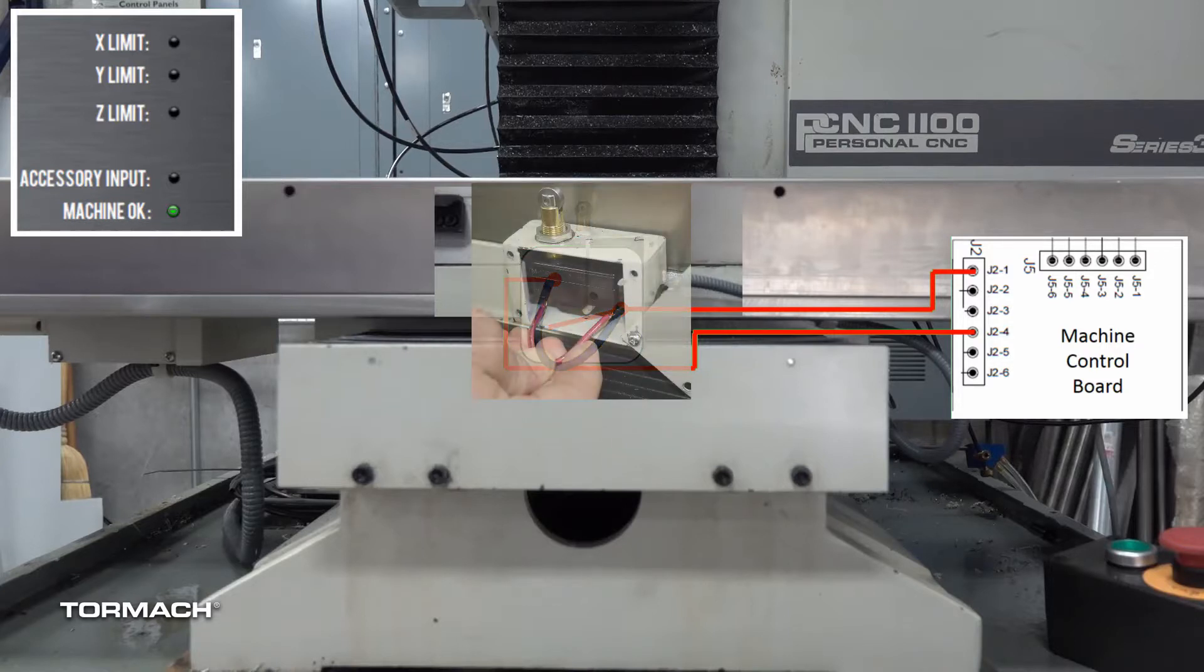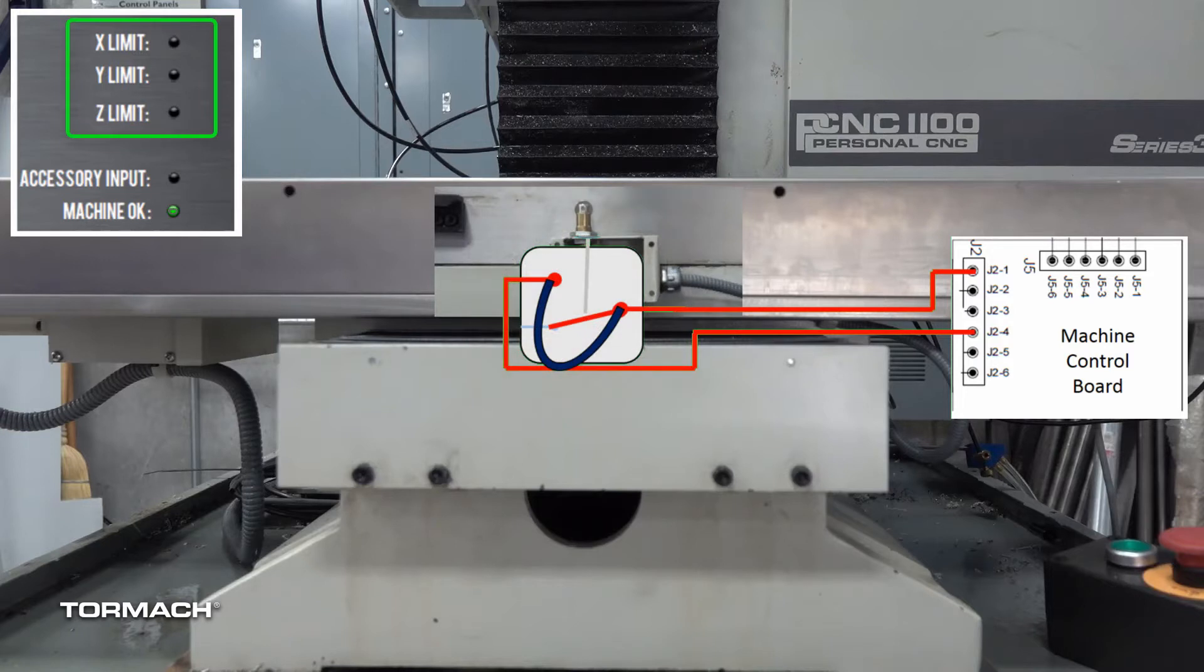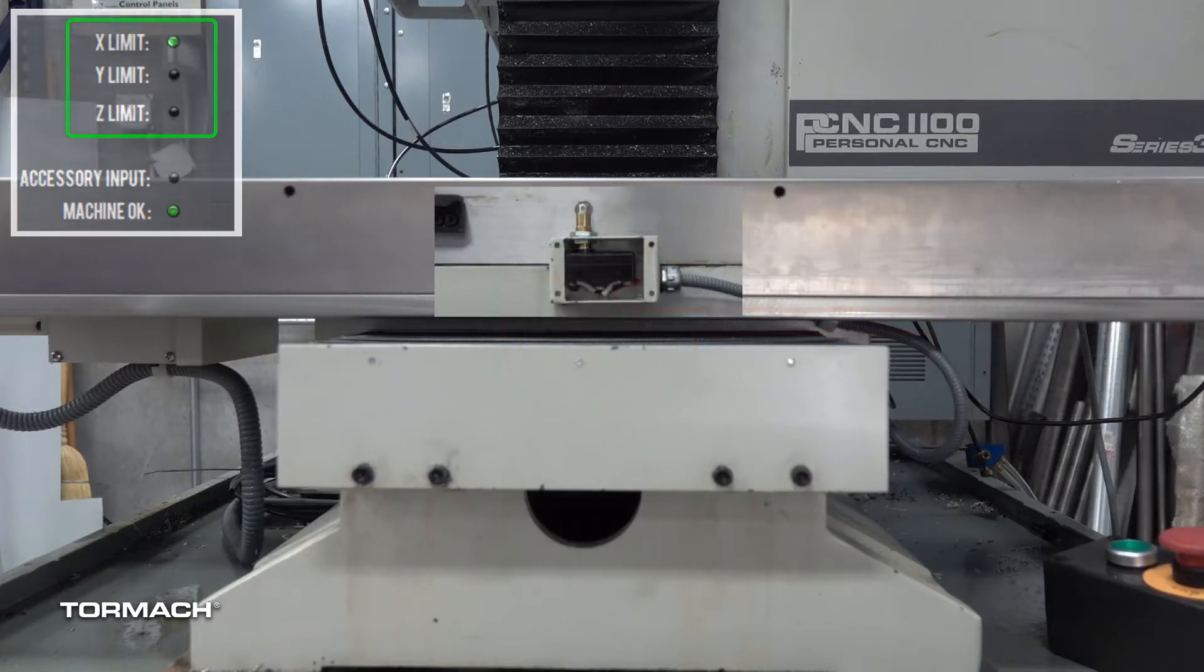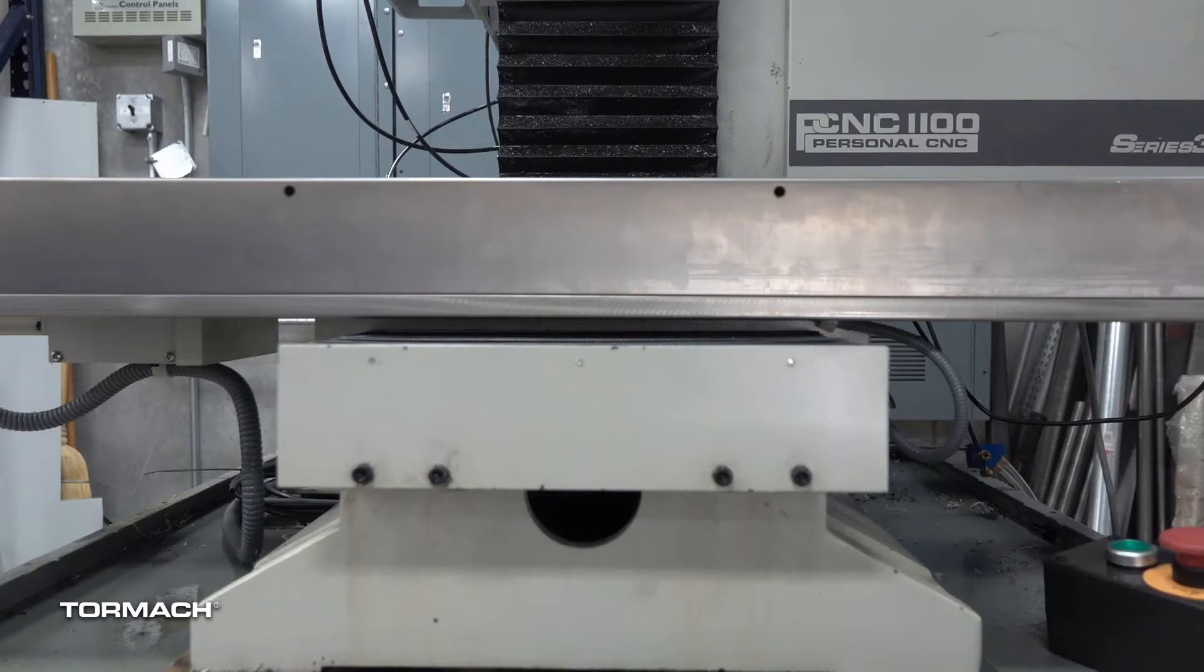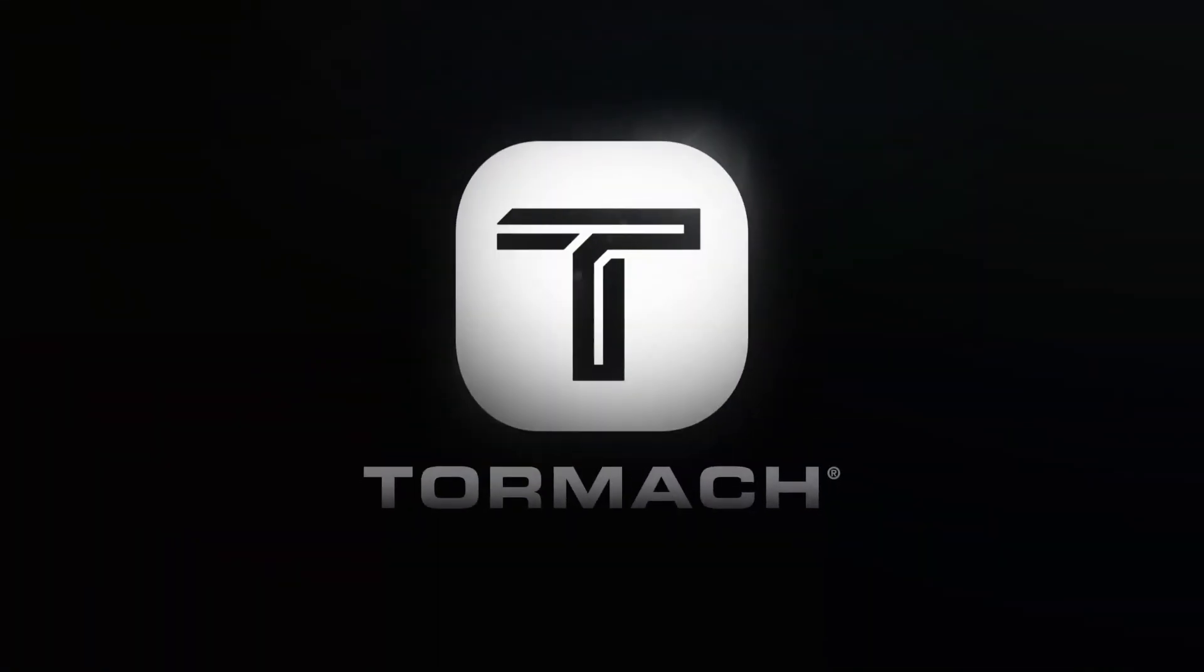If the PathPilot limit switch indicator goes out with the jumper in place, we can isolate the machine control board, the limit switch, or the circuitry as a potential problem.